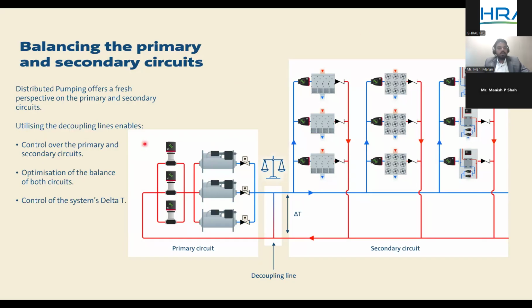The primary pumps are designed only to handle the flow within the primary loop. So we have a decoupler, which acts as an intermediary between the primary and the secondary. The primary pump does the job till the decoupler, and each secondary pump will take the chilled water or drive the chilled water from the decoupler to that particular node and send it back till the decoupler. That's how we clearly define the primary and secondary side of the circuit, and each does its job to balance the flow based on change in the load.